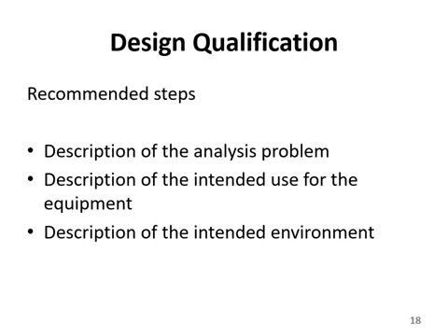There are a few steps which, if you are following while doing the design qualification, help you a lot, right? So what is helpful is that just describe the analysis problem. If you're getting some problem, describe it. Describe the intended use of the equipment. If you are using an equipment, what is the intended use? Design it properly. Intended environment क्या है? So describe the intended environment, the environment where you're going to use the machine. That is also important. Describe it.